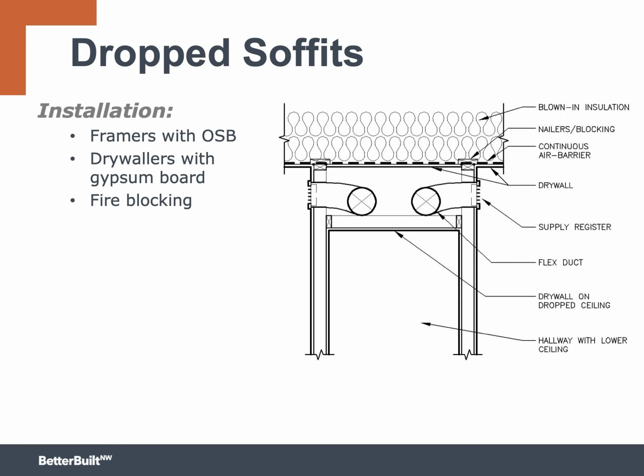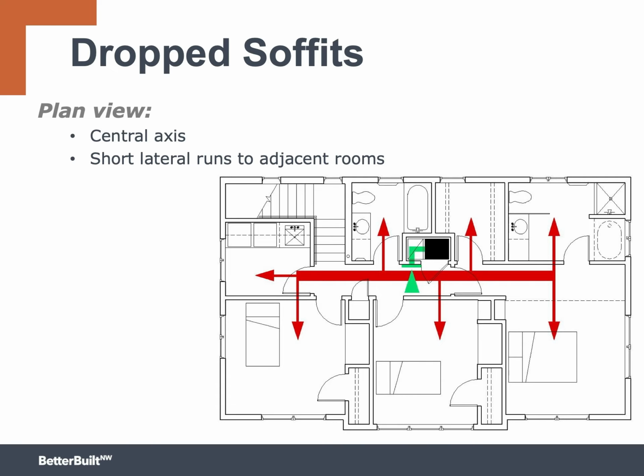Fire blocking in this case could be provided by solid wood blocking in the walls at the same level as the lower ceiling. Or you could line the entire soffit with drywall around the inside to create the proper fire rating for the cavity. As I said, the central hallway is a good place to locate a drop soffit. It gives easy access to most or sometimes all of the rooms. Supply registers can be located on the interior walls. Soffits may already be planned above the kitchen cabinets and can usually be added to bathrooms without being obtrusive.